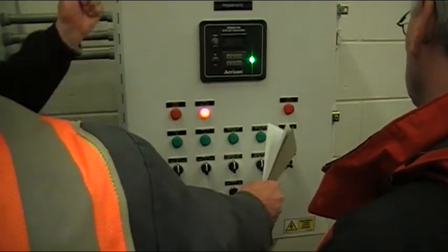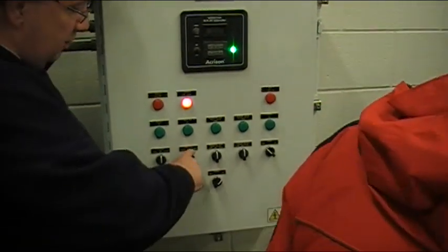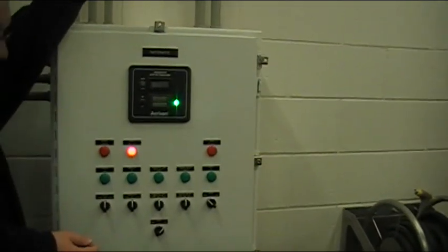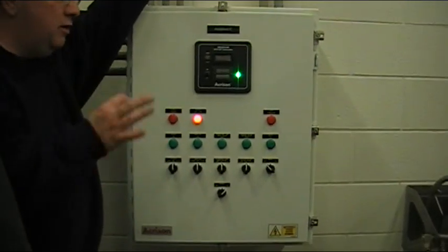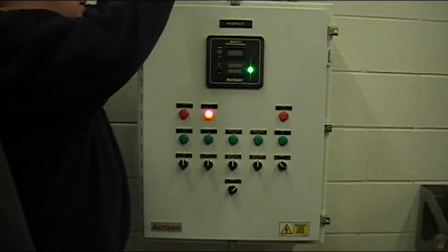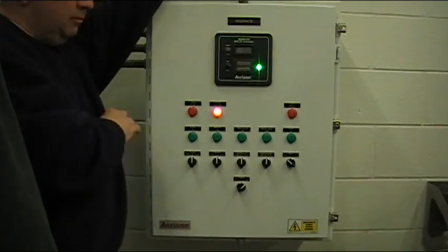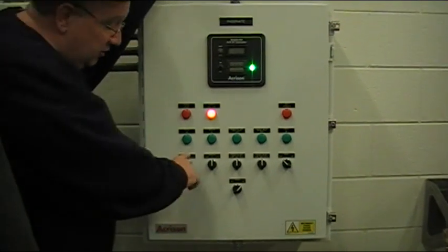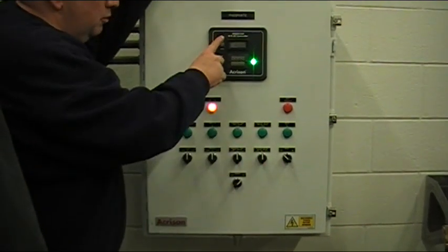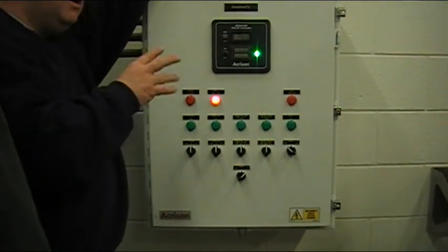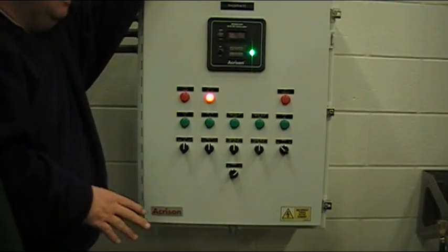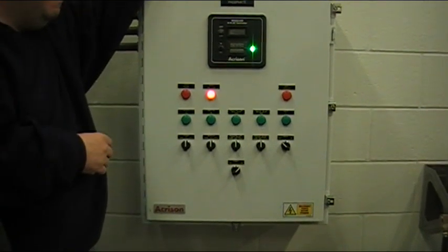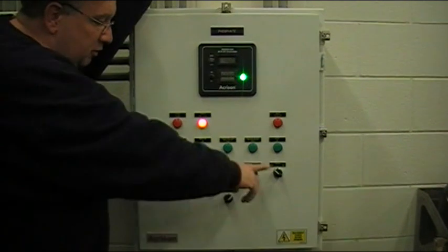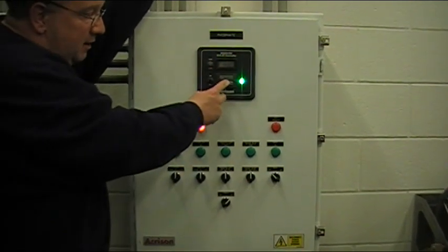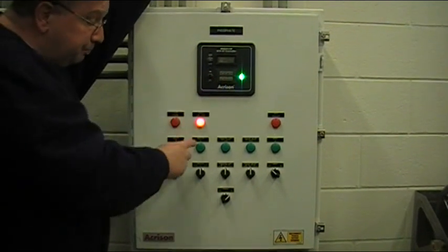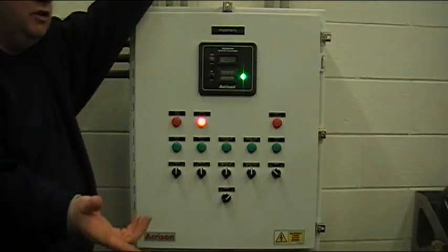Everything else has to be on, make sure it's on. All your switches here have to be in the auto position for the SCADA system to run this system. That's true of this system, the Fluoride system, and the Permanganate system, they're all the same. The key is, it's not just these switches, it's also this switch. You can't sit here and say, I don't want the SCADA to control my 4 to 20, I want to do it from here. Well, you can't put it to auto. When you put this to hand, then you use the thumb wheel here, just like we were here. When you're using auto, you get the signal from the SCADA.